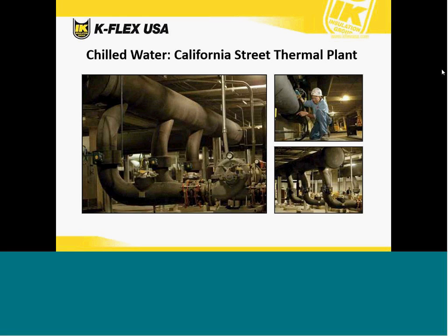We've got pictures showing complex geometries and the large and small pipe that were insulated. You can see that there were some pumps, piping, valves, and other fittings that were insulated here. The flexible feature of the product made insulating those fittings and complex geometries relatively easy, and time has shown that it's held up very well over those 10 or 12 years that it's been installed, with no failures or condensation forming.